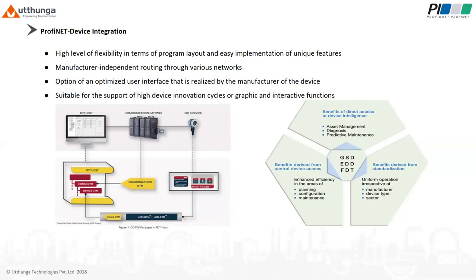FDT technology provides a standardized communication interface between field devices and monitoring systems, used for configuration, maintenance, and diagnostics. The key feature of FDT is its independence from any communication protocol and the software environment of the host system. FDT technology allows any FDT-enabled device to be accessed from any host using any communication protocol. These are some advantages. In the right side image, you can see the advantages of GSD, FDT, and EDD lined up. This is actually a huge topic: GSD, EDDL, FDT, DTM. We have briefed it in a short manner right now.